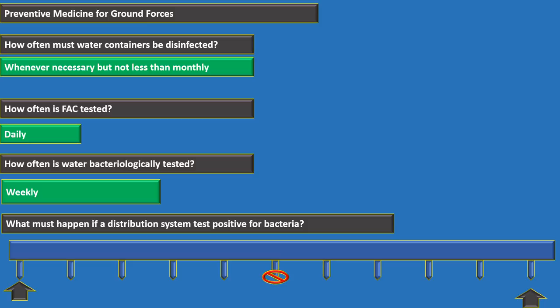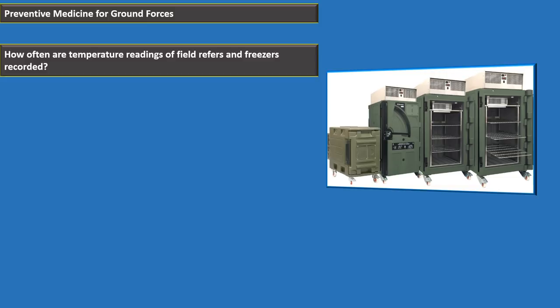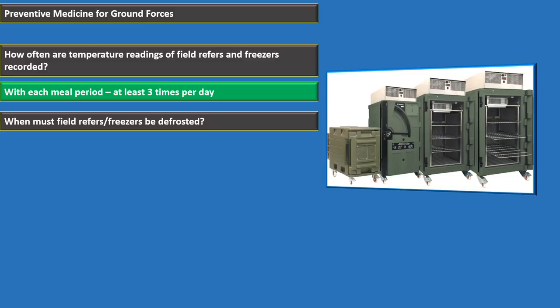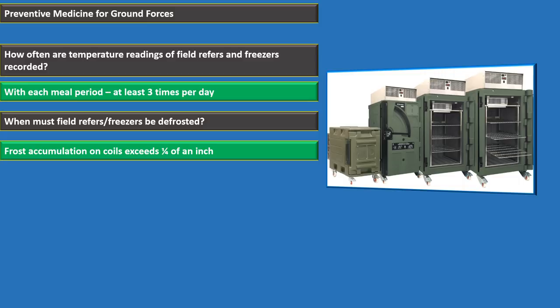Temperature readings on field refrigerators and freezers must be recorded with each meal period or at least three times per day. Field refrigerators must be defrosted when frost accumulation on the coils exceeds one-quarter inch. Field reefers must be held at 40 degrees or below.